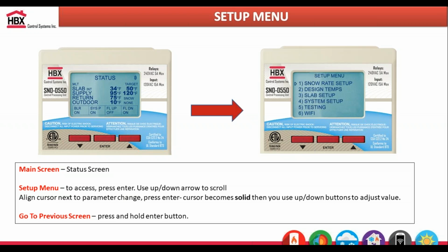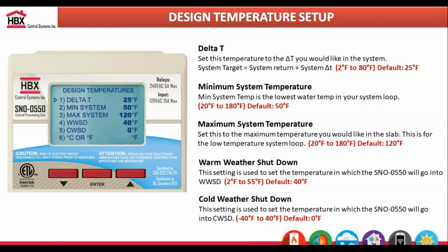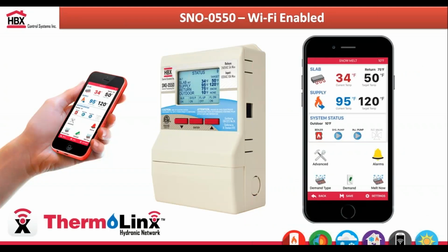So here you can navigate your snow rate setup. You can adjust your delta design temperatures. So this is your min and max system temperatures. You can set whatever delta T you want for in and out of that slab, and you can adjust your warm weather and cold weather shutdown options on there.